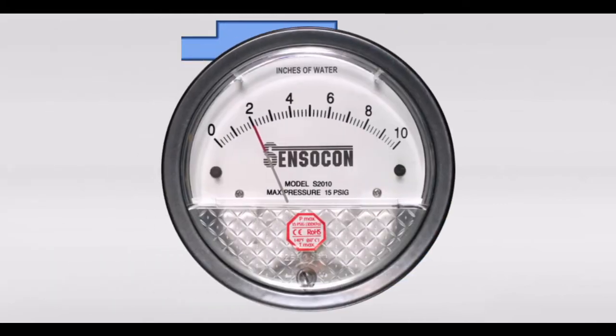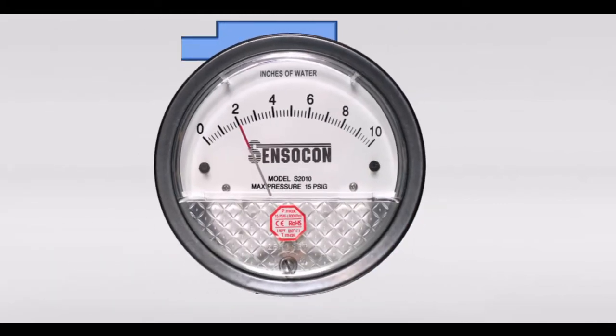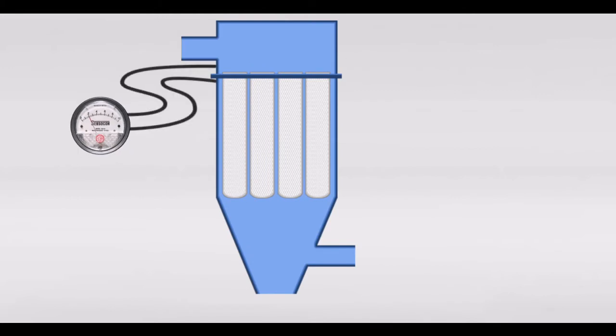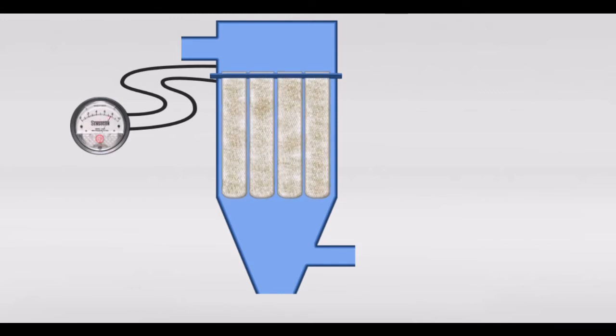With the use of a series S2000 differential pressure gauge, you can accurately see the increase in differential pressure across the dust collector's filters as it loads with debris and dust. This allows the user to know when it might be time to change or clean the air filters.